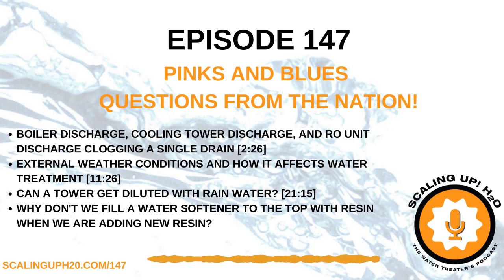This is especially common if you have a condensate drain, maybe your air conditioning system at your house or an ice maker. They have low flow, but they do have water flowing through them, and biologicals will set up camp in there, grow, and plug the drain. Now, as a water treater, we've put some sort of biocide in that system, maybe a little capsule that time-releases a bit of biocide to keep the drain clean on an HVAC condensate drain. I've even seen people use bleach solutions to rinse out those condensate drains every so often. So perhaps something like that is going on.